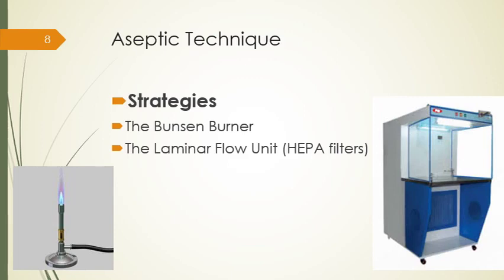The laminar flow unit, also called a hood, is a sophisticated appliance that can help prevent contamination of reagents and biological cultures if used correctly. It provides the workspace with clean, ultra-filtered air, keeps room air from entering the work area, and both suspends and removes airborne contaminants introduced into the work area by personnel. The most important part of the laminar flow hood is a high-efficiency bacteria-retention filter, also called HEPA. A certified HEPA filter must capture a minimum of 99.97% of dust, pollen, mold, bacteria, and any airborne particles with a size of 0.3 micrometers at 85 liters per minute.